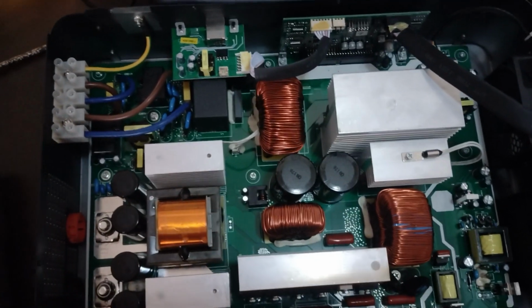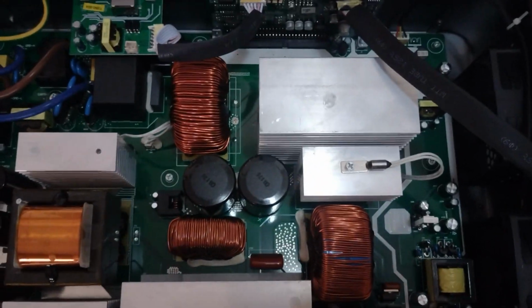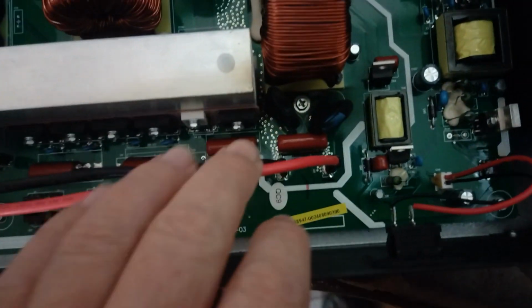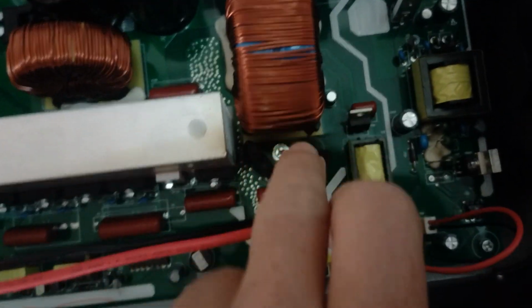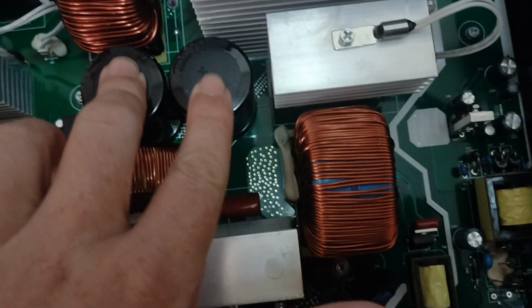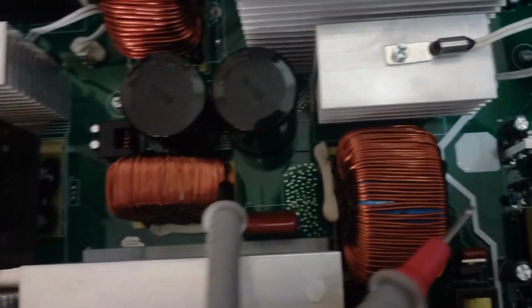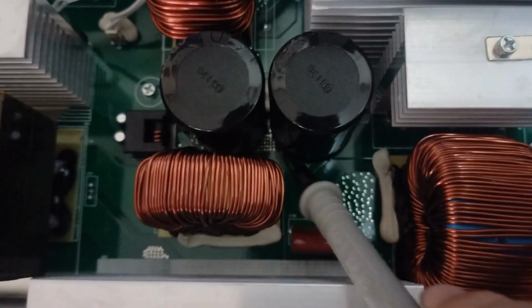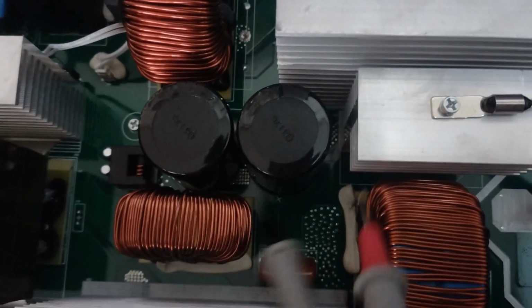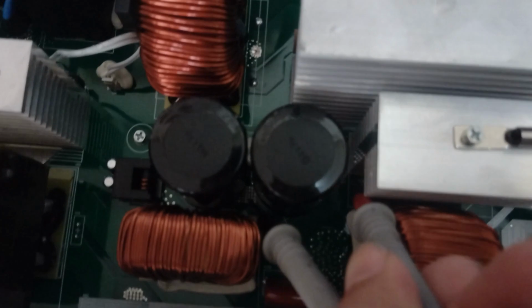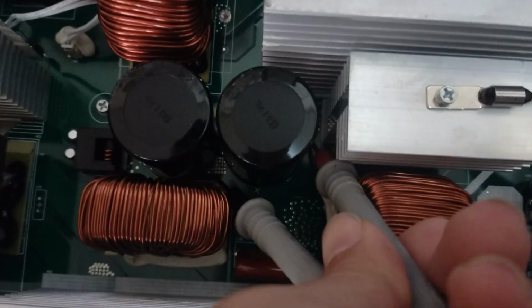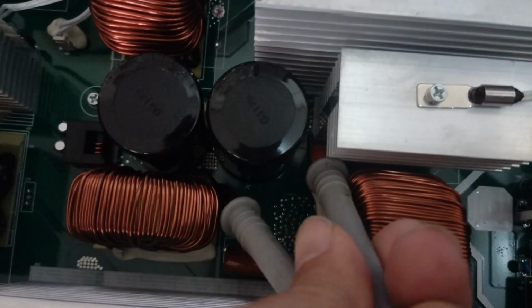So this is what's typically inside of a MPPT inverter. There's a few different stages. This is the solar input. It basically goes straight through the inductor here, which is a boost or buck converter, and into the high voltage bus. That's about a 380 volt bus usually, maybe a bit higher. And we've got some pads here, you can see down there, that'll be positive, and down there is negative. So we can measure resistance across the bus. Maybe hard with one hand. There we go. And yep, we've got a dead short.